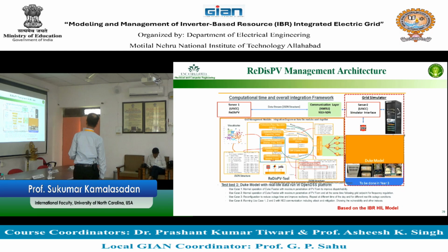What we did was develop a tool, and that tool is this. That tool communicates with the real feeder, and data is transferred through Python scripting to deliver the set points. What is that communication? Same thing, hierarchical. Take the feedback from the local, go to the central substation, then make it into areas, give the signals to the area, and from the area, give the signal to the individual local DER.